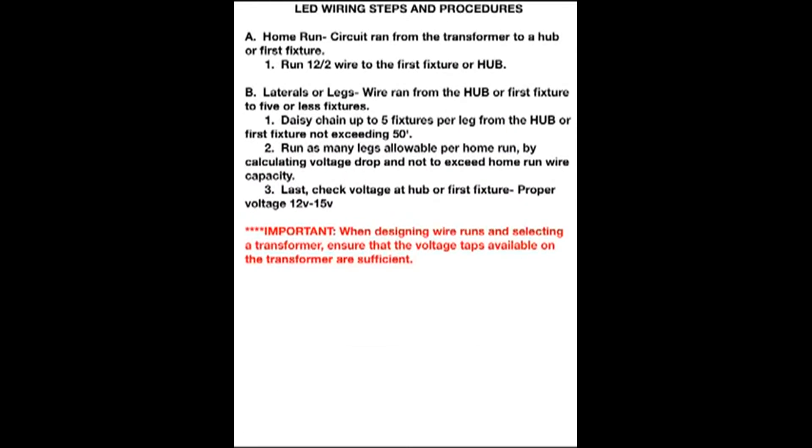Importantly, when designing wire runs and selecting a transformer, ensure that the voltage taps available on the transformer are sufficient. Make sure you have a high enough voltage tap on that transformer to compensate for the voltage drop.